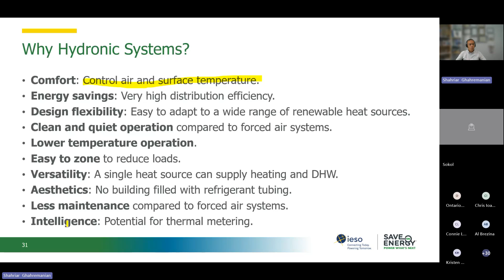They provide energy saving. This is a hydronic system inside the building, so it's better to combine our heat pumps with these hydronic systems. They can work at the low temperature we want, reduce loads, and require less maintenance compared to forced air. These days we can have thermal metering because it's water, whereas for air it's hard to measure since we'd need flow rate and temperature measurements. But for water pipes, especially in multi-unit residential buildings, we can meter how much hot water we provide to each unit, even for charging purposes.